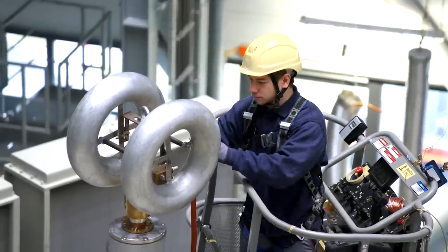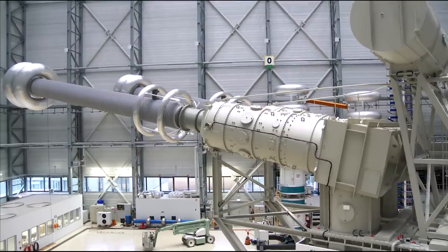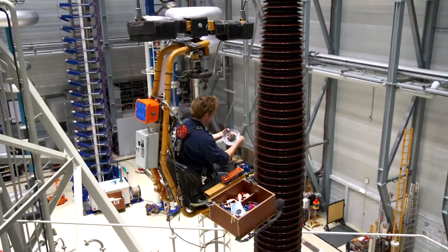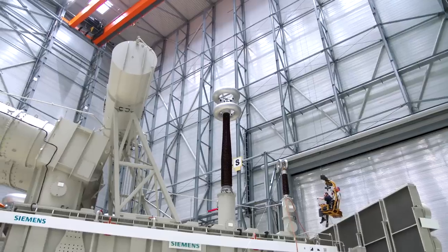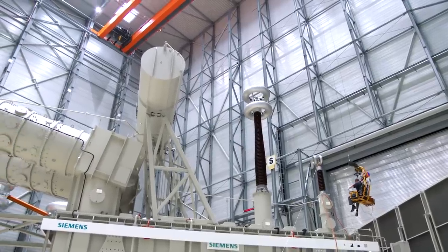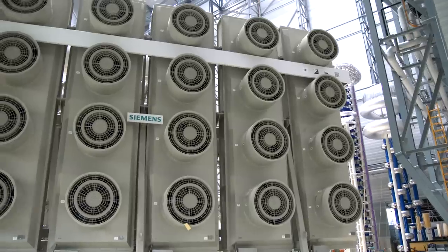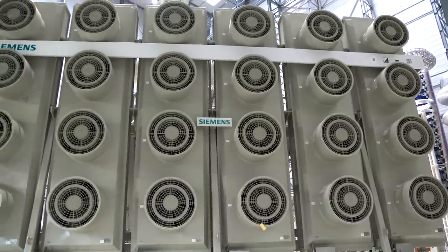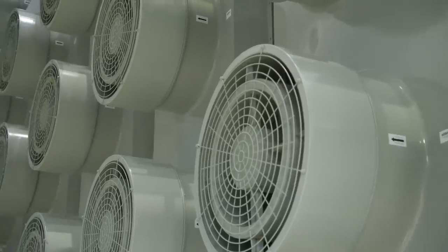To achieve this feat, the engineers had to develop a valve lead system, as well as the overall transformer design itself. The result is a giant step forward, at a 55% increase of rated power of the single phase transformer. These transformers feed into a transmission system at a voltage level of 1,100 kilovolts direct current, transmitting electrical power of 12 gigawatts.